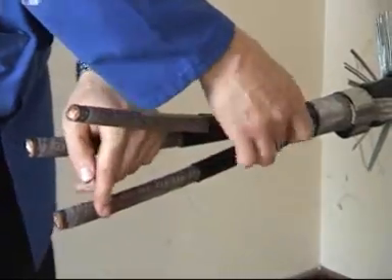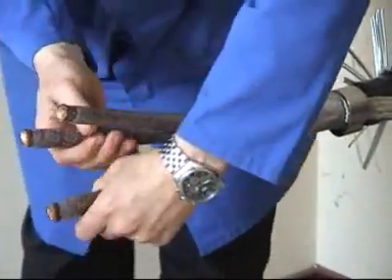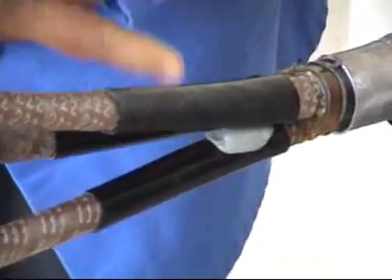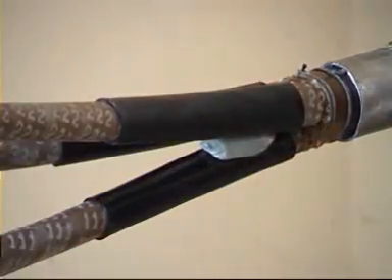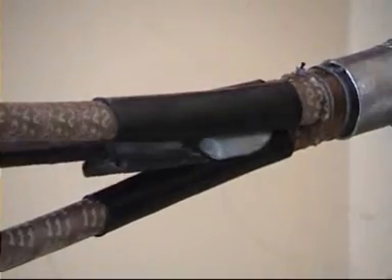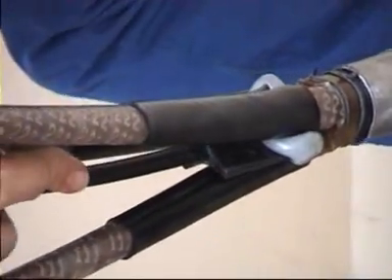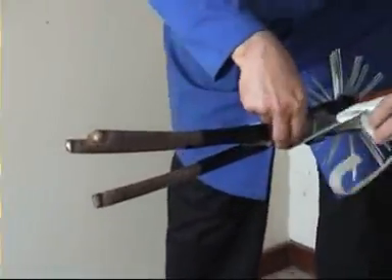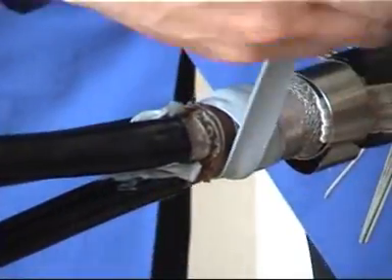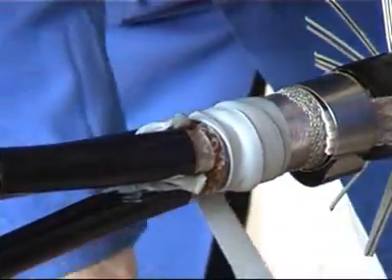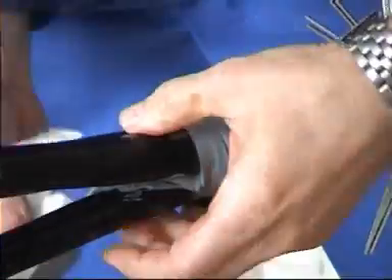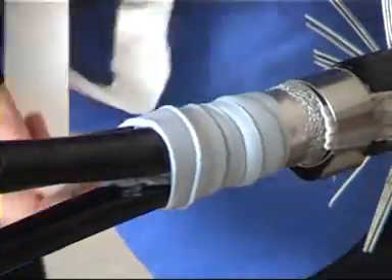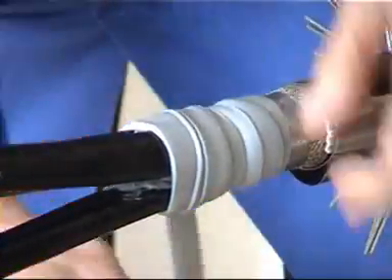Take the grey mastic crutch wedge, insert it into the crutch of the cable, and push down as far as possible. Apply grey mastic tape around the lead sheath cut, extending onto the conductive tubes and lead sheath. Do not tape over the roll spring, as we need this to make contact with the conductive boot which is fitted next.